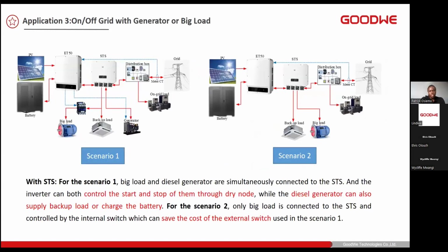Yes, option 3 is, well, in case you have a big load, and then you can do option 3. So scenario 1 for option 3 will be a big load with the diesel generator with an STS, and a control start and stop through a dry node. The diesel generator can work as a backup or charge the battery. For scenario 2, this is just for the big load, and the STS also needs to be integrated with the internal switch. And then, yes, this saves the cost of including an external switch.